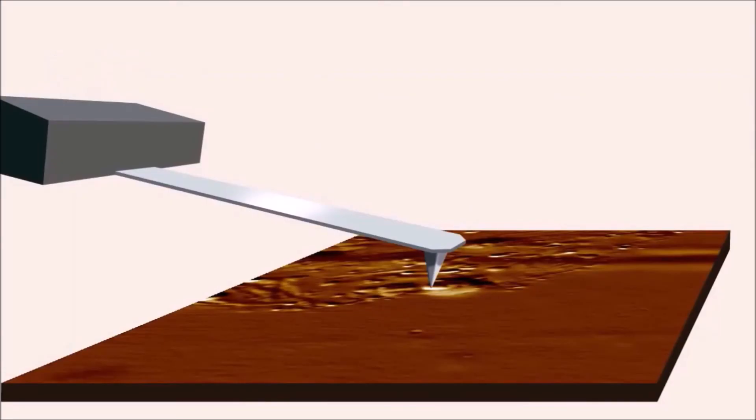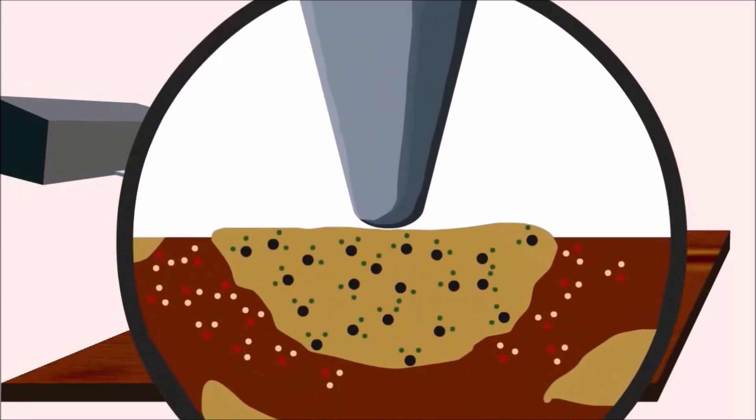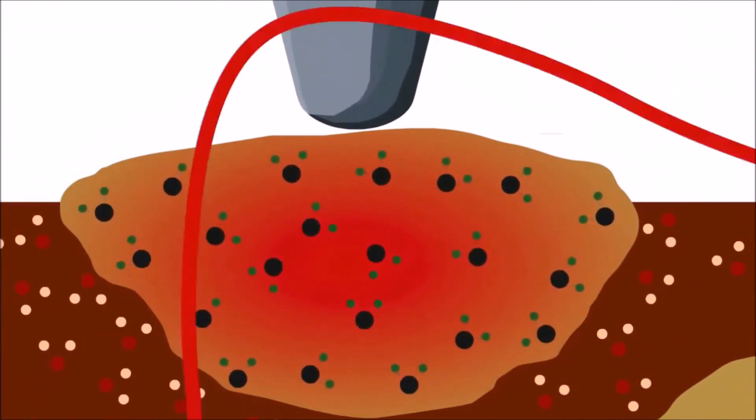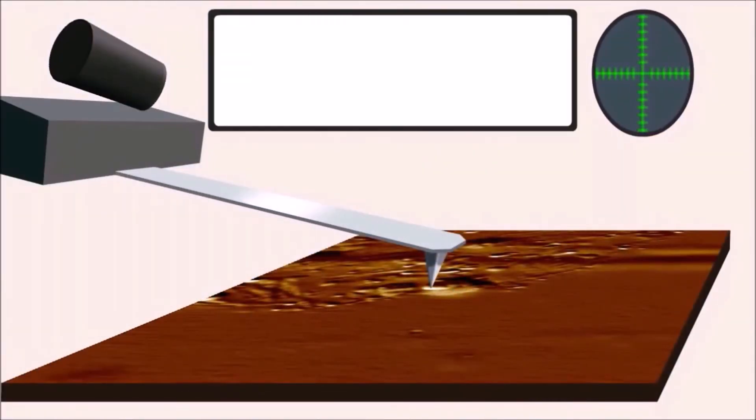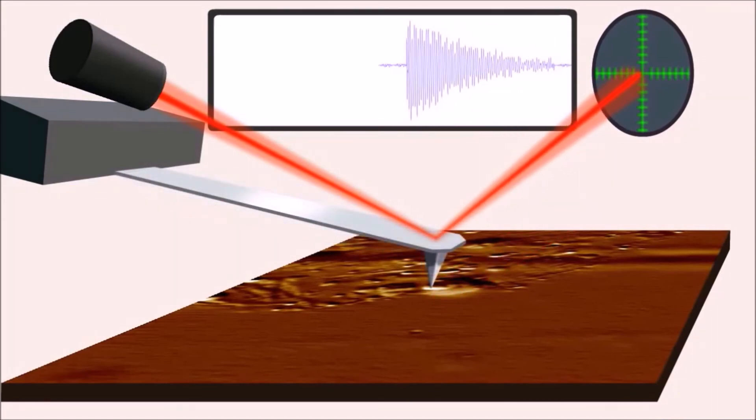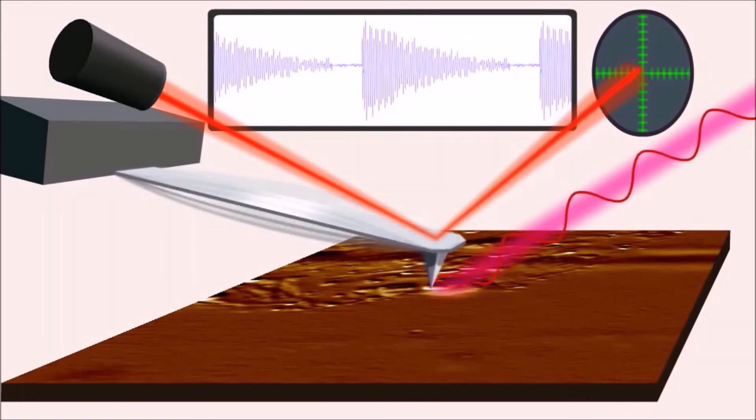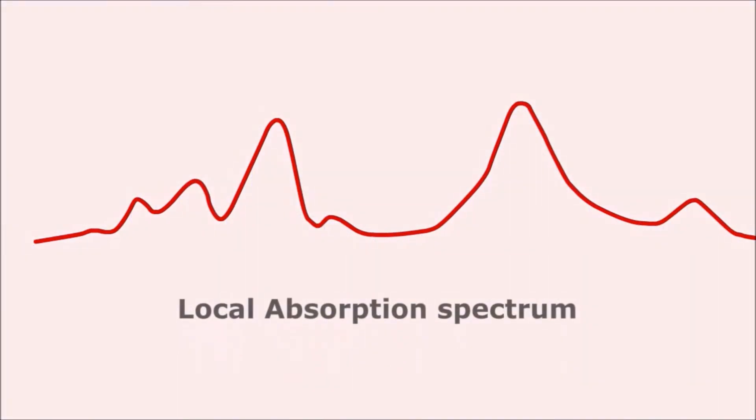This animation shows the overall working principle of AFM IR. IR light is incident on the sample. The incident light causes thermal expansion. This thermal expansion causes instantaneous oscillation in the cantilever which is recorded through another laser and a detector. From the cantilever oscillation, we get the local absorption spectrum.